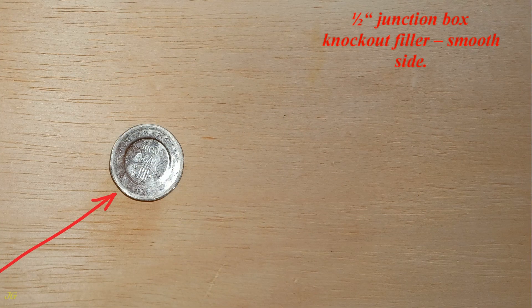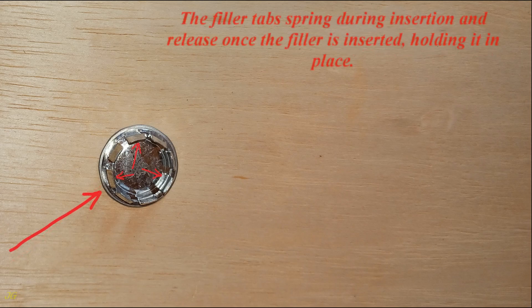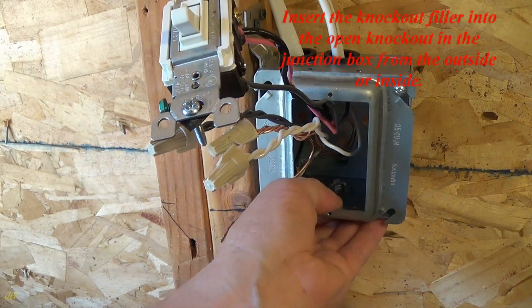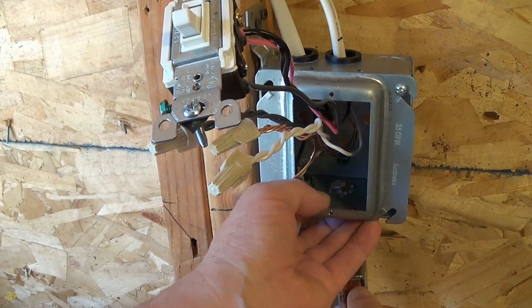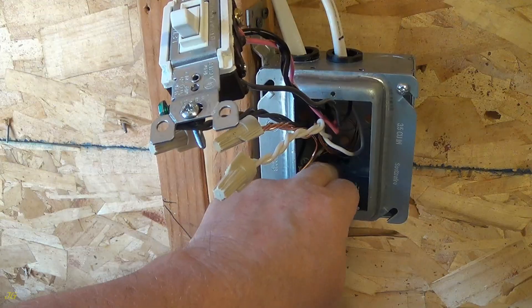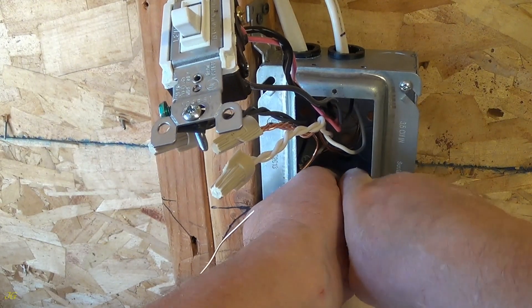A ½-inch junction box knockout filler has a smooth side and a spring tabs side. The filler tabs spring during insertion and release once the filler is inserted, holding it in place. Insert the knockout filler into the open knockout in the junction box from either the outside or inside. The ½-inch knockout filler is now inserted into the open knockout.